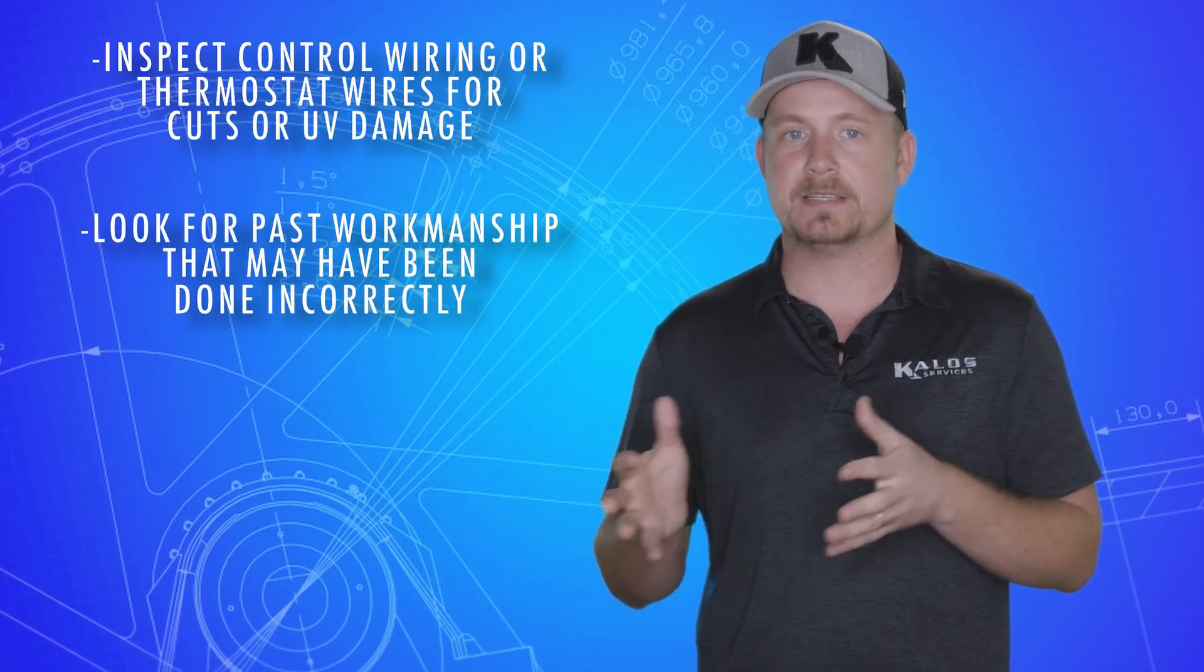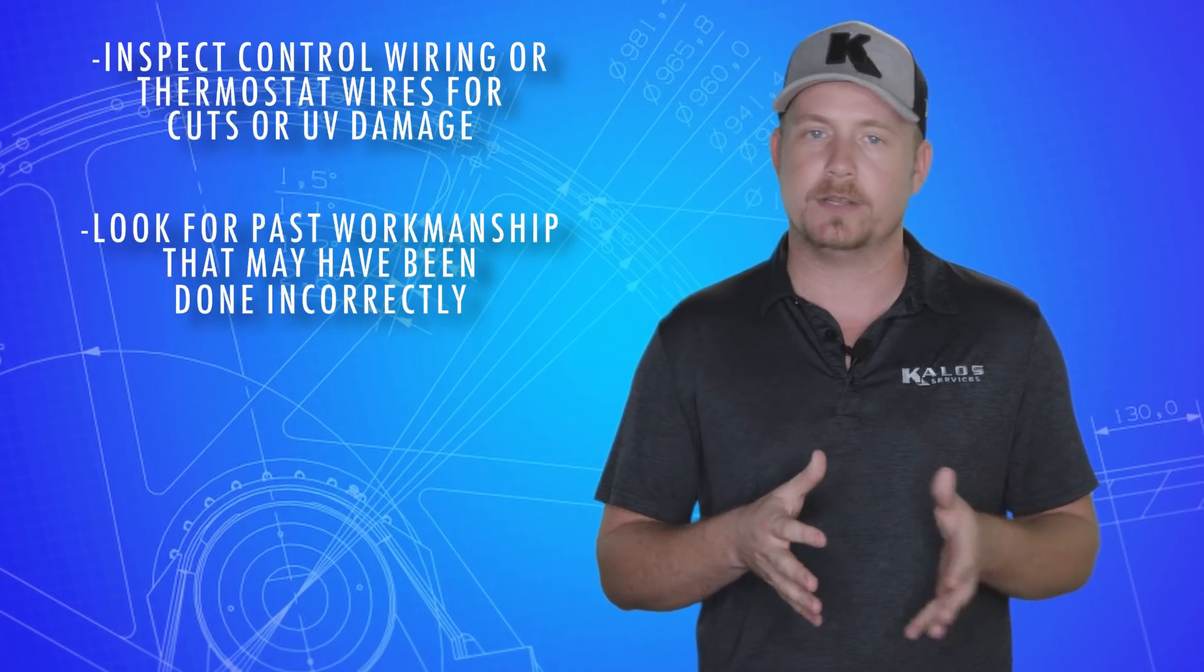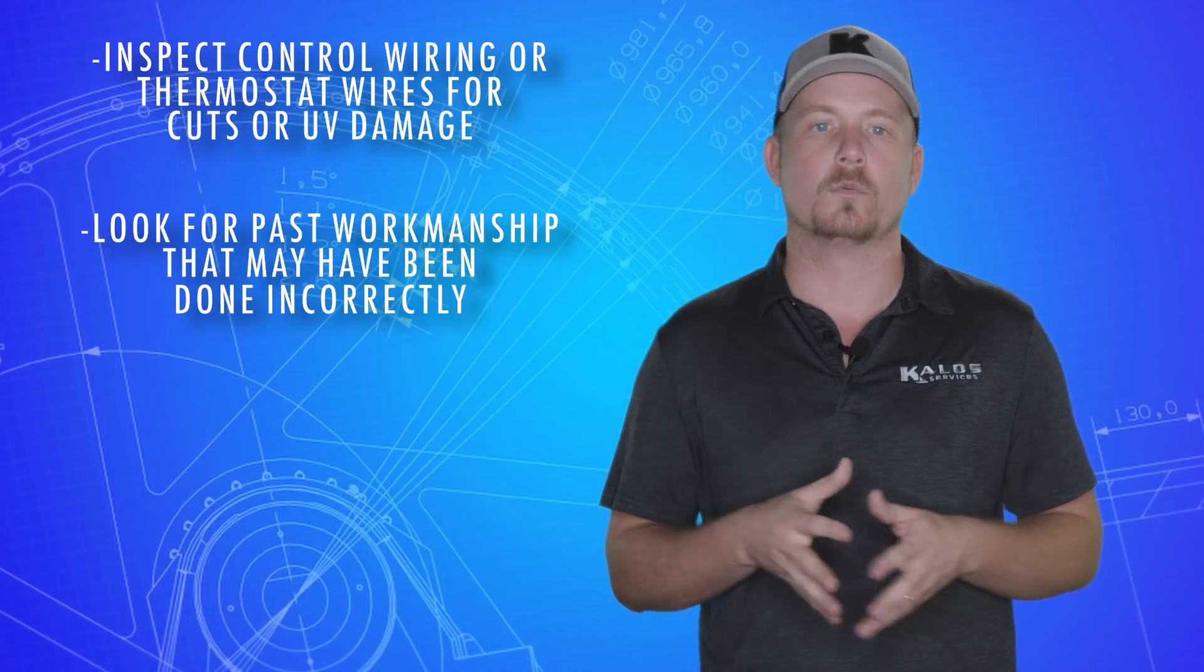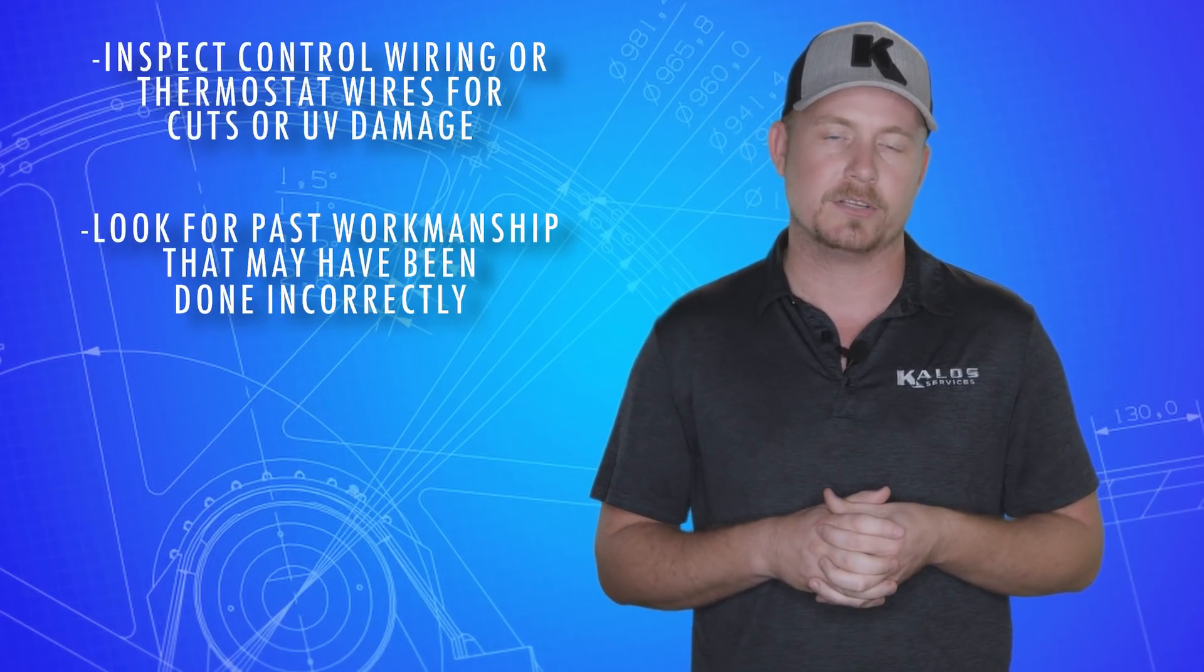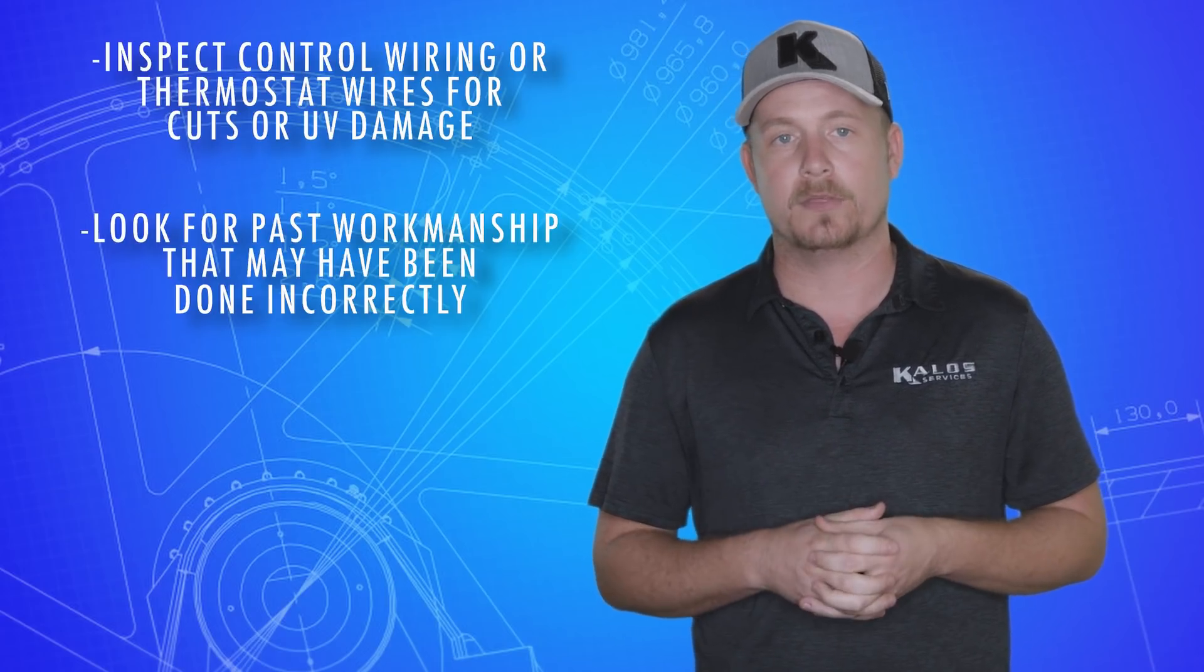Look for past workmanship that may be done incorrectly. Just because that fan motor or capacitor is new doesn't mean it's the right size and wired properly. Always double check your own work as well as work done by others. And when in doubt, confirm with the manual.